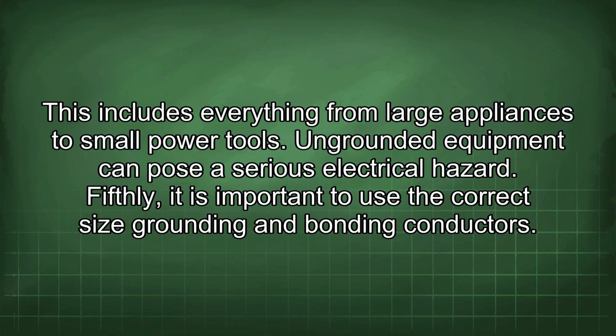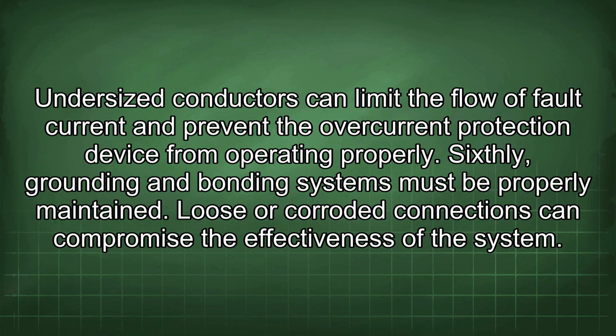Fifthly, it is important to use the correct size grounding and bonding conductors. Undersized conductors can limit the flow of fault current and prevent the overcurrent protection device from operating properly. Sixthly, grounding and bonding systems must be properly maintained. Loose or corroded connections can compromise the effectiveness of the system.